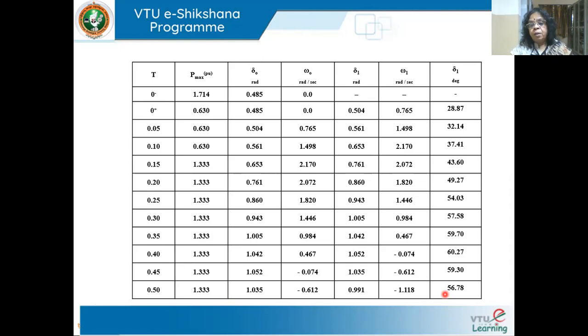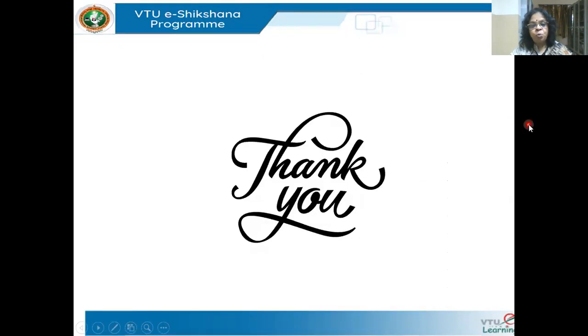So now you see here, I have simulated for one fault, a three-phase short circuit at the midpoint of the line. So you think of in a big system, how many types of faults you can have. Right? It can occur on the transmission line. It can occur at the buses. It can be a three-phase fault. It can be a single line to ground fault, everything. So you take all the critical faults, major faults, and then rank them, which is the worst, and plan your system for that.